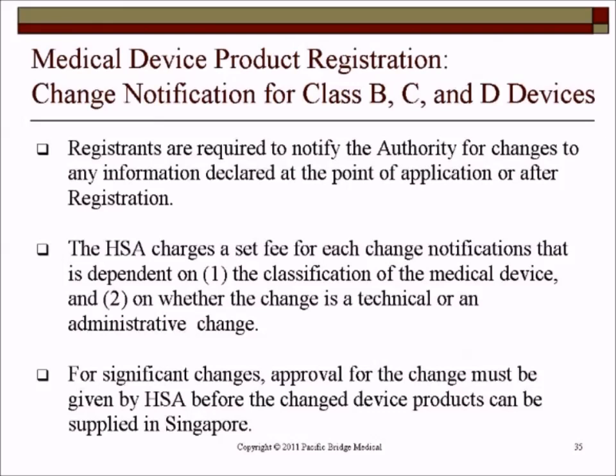Other changes that involve critically the indications for use and the intended use need to be backed with the necessary data itself, clinical and preclinical, depending on the type of change required. If there are changes that are really significant and different from your product itself, HSA may decide that this is also a new product registration. So if it's a very key change to the indications for use, one needs to be aware that the change notification may not be suitable.